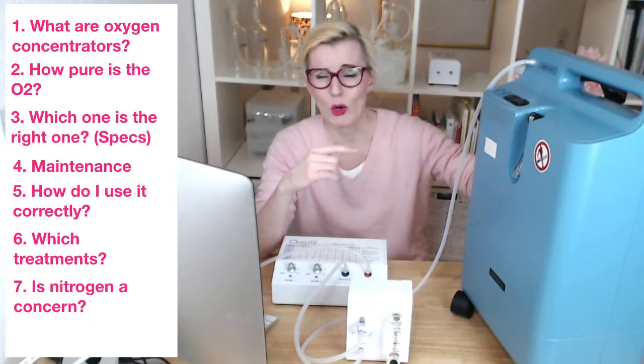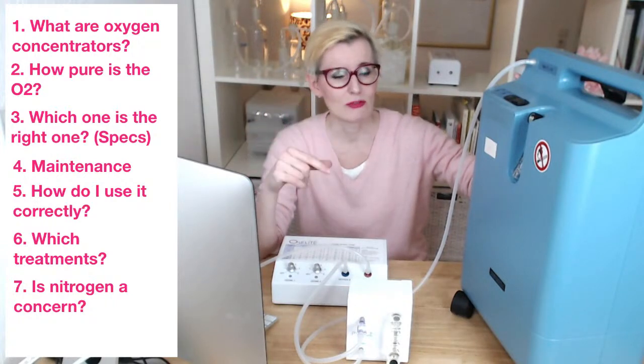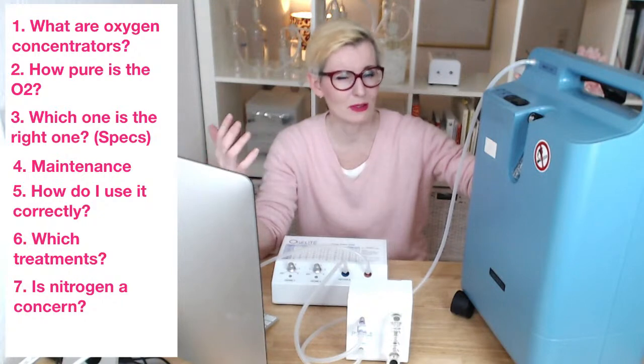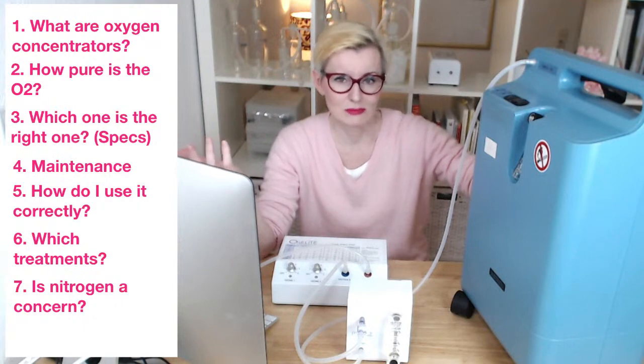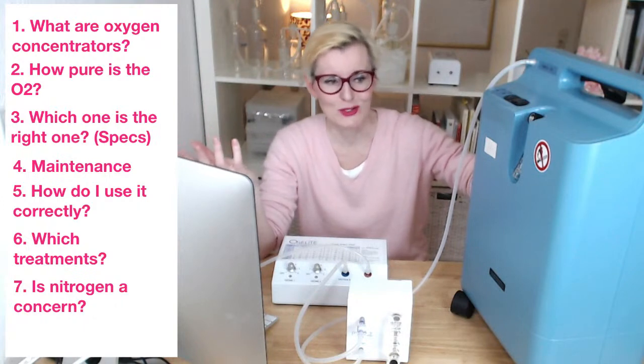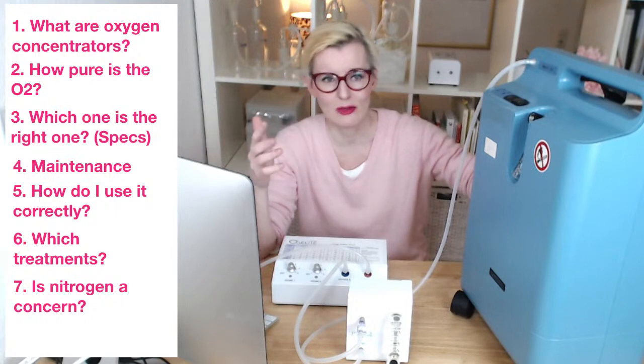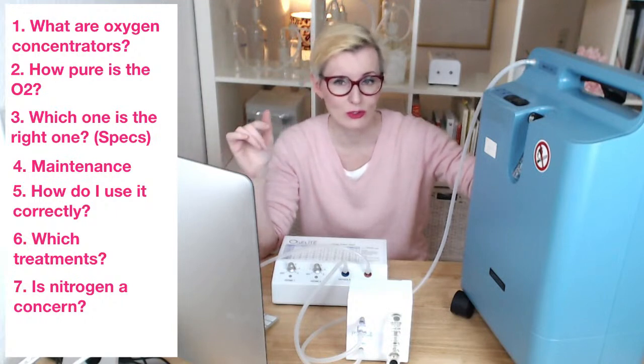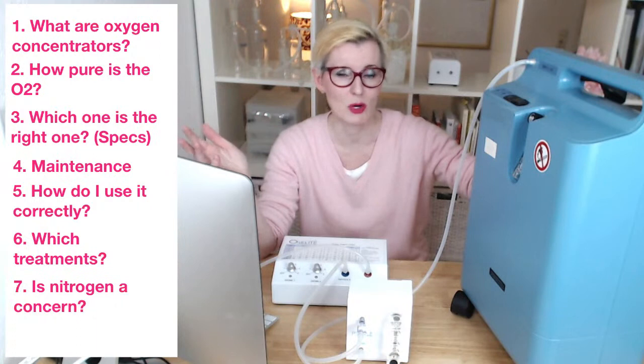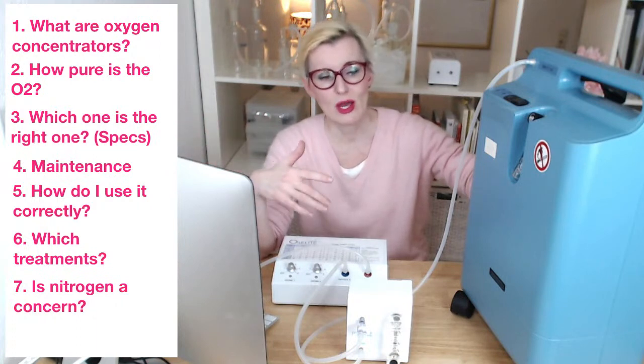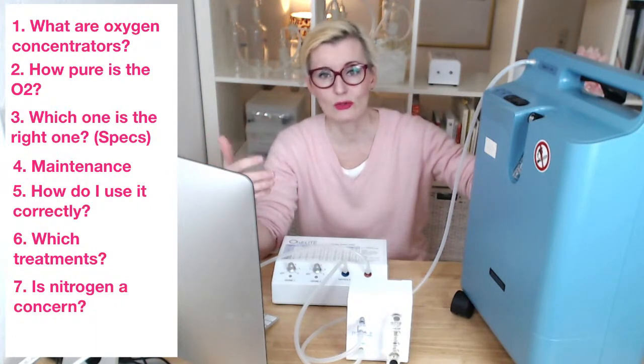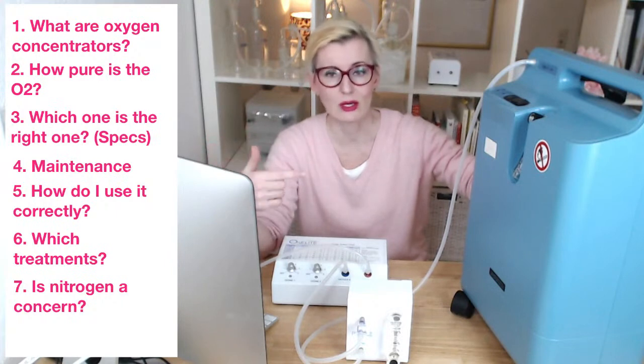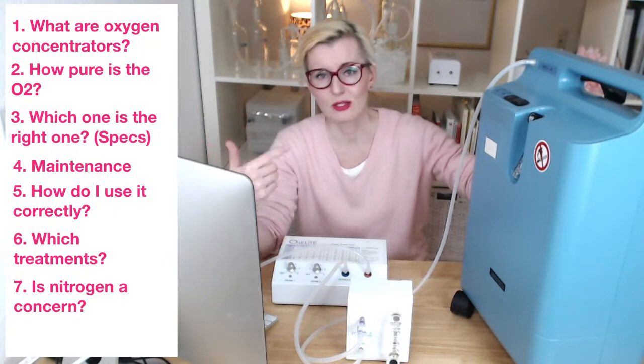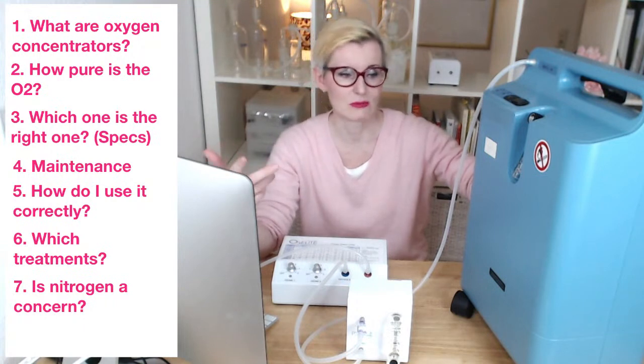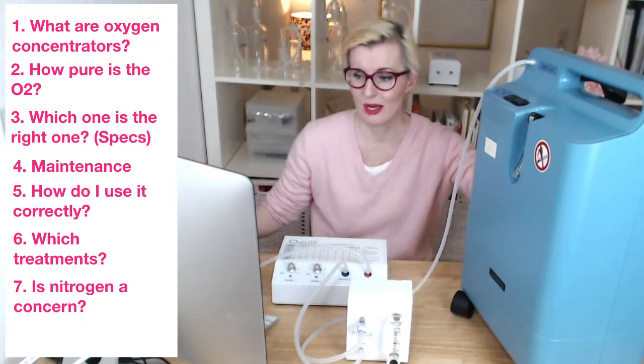And I believe there's some oil inside, and if the machine is not used for a longer time, then something can happen with the oil. It can get old. So let's say if you don't use a concentrator for a few years and you then try to turn it on, then it's possible that it will not work. So he said that it's a good idea to just turn it on regularly, to make sure that the motor inside just runs for some time every week.